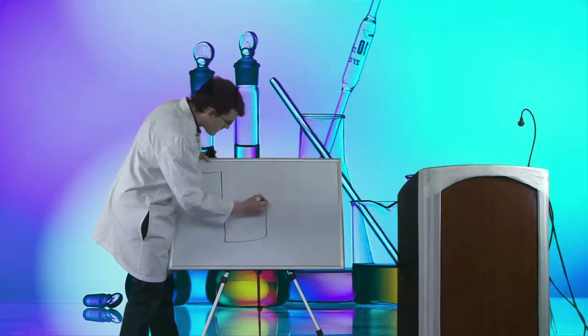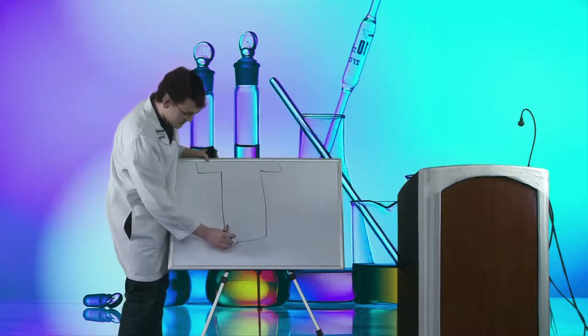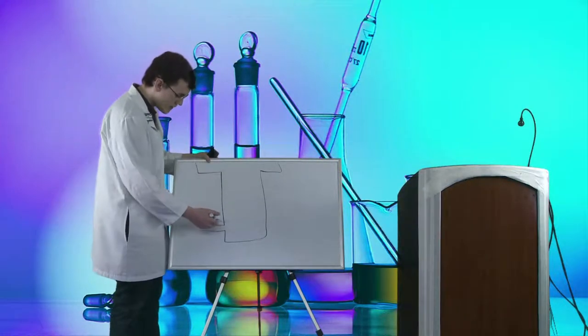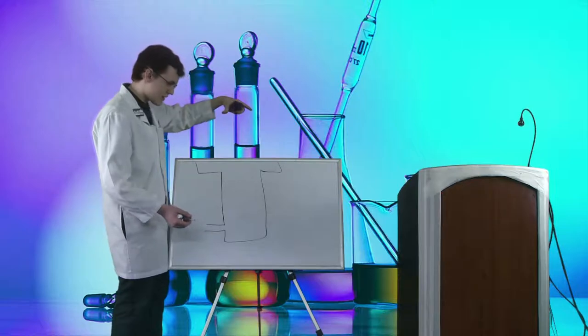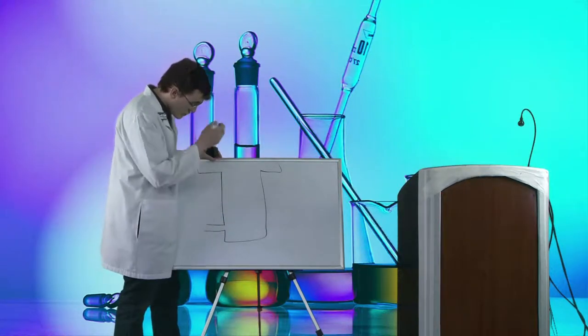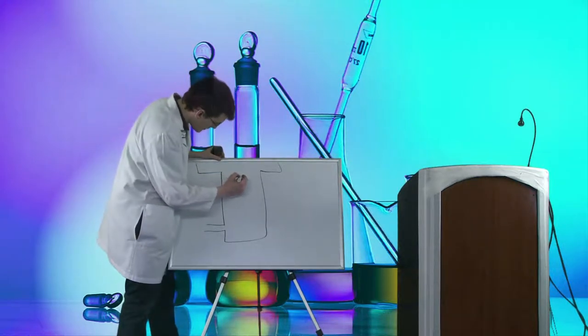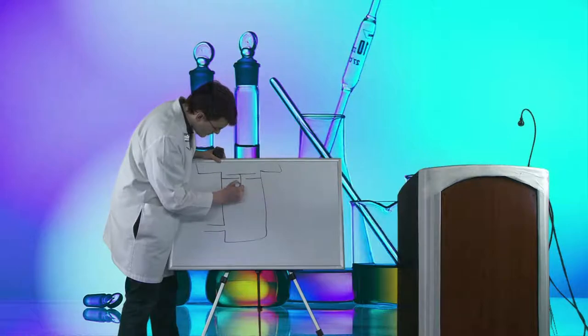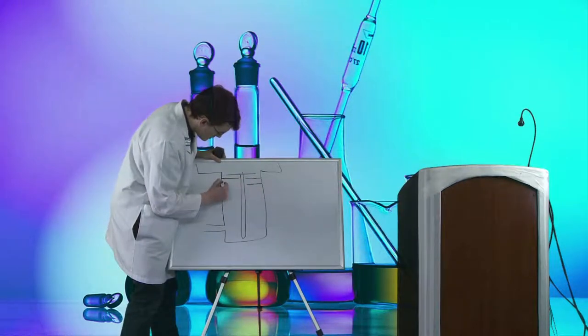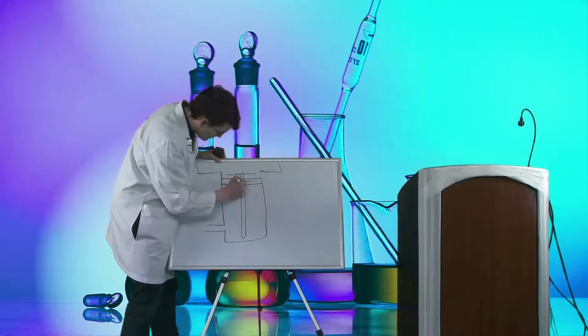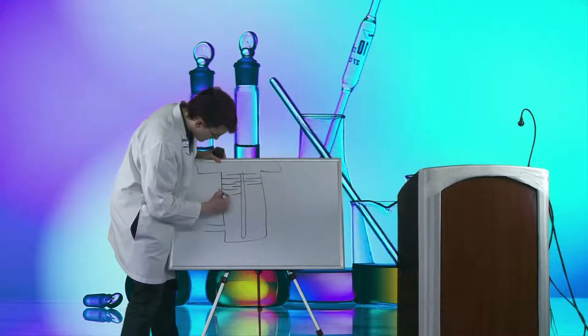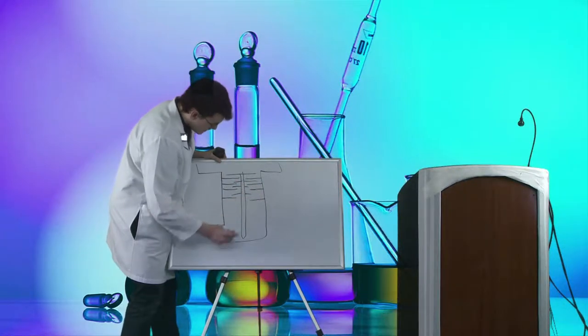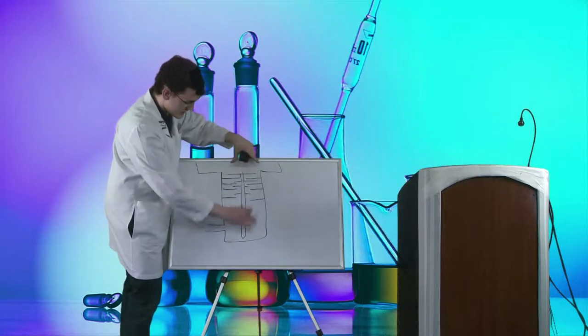The reason rotary pumps are called backing pumps is that they back a high vacuum pump. Once again, we'll have a high vacuum on top and low vacuum on the bottom. Instead of oil vapor, this time we have a spinning rotor. It looks like a jet engine from the top — a bunch of blades. We have fixed blades on the side and a rotor down the center, with many stages. We've got larger rotors toward smaller rotors continuing down the entire length of the pump.